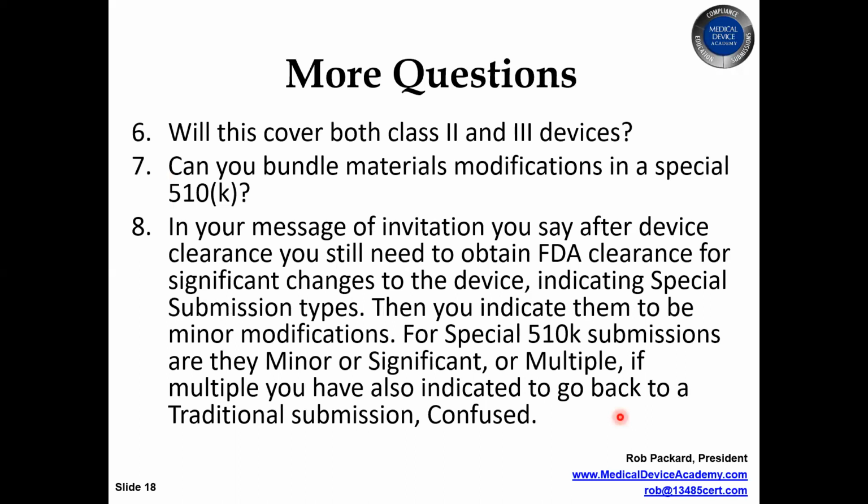However, if you were making a change in materials where you already were using that material in another product, and so you didn't need to present any new biocompatibility data, and the only question mark was, would it be mechanically sound, would it have the same mechanical performance, you would do the verification testing over again for the mechanical performance of that device, make sure it's okay, and submit it to the FDA as a special.